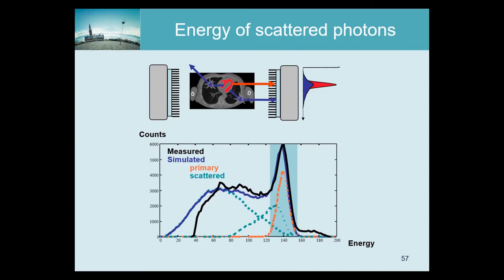Could it be signal pile up Johan? Yeah, so more than one photon arrives and the gamma camera thinks they arrive at the same time, so the scintillation of the first is still busy while the scintillation of the second is added and those energies are added. And since most of the photons will have less than 140 kiloelectron volt, the probability of the pileup, or the average value of the pileup, is much lower than 280. So every now and then it will happen that two primary photons arrive, but the probability is much higher that lower photons are combined. So they end up here, which is the reason to check the energy and not only reject the low energy photons but also the high energy photons. The simulator didn't bother to simulate such effects.